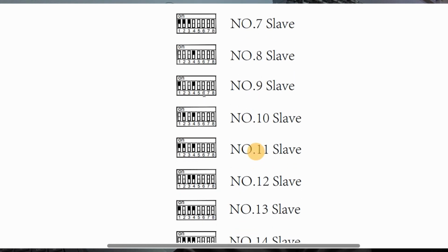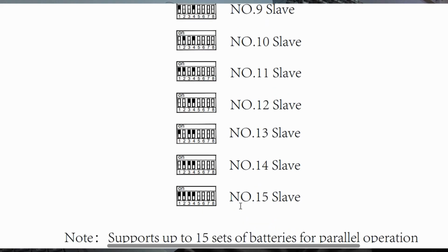Battery 8, dip 4 in the on position. Battery 9, dip 1 and 4 on. Battery 10, dip 2 and 4 on. Battery 11, dip 1, 2 and 4 on. Battery 12, 3 and 4 on. Battery 13, dip 1, 3 and 4 on. Battery 14, dip 2, 3 and 4 on. And then lastly, battery 15, dip 1, 2, 3 and 4 on.